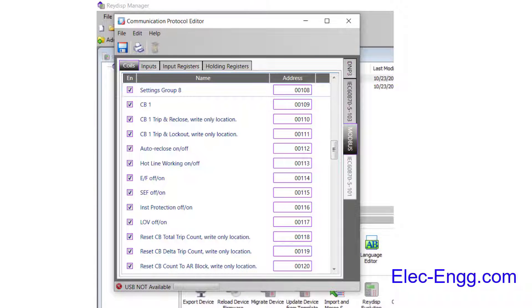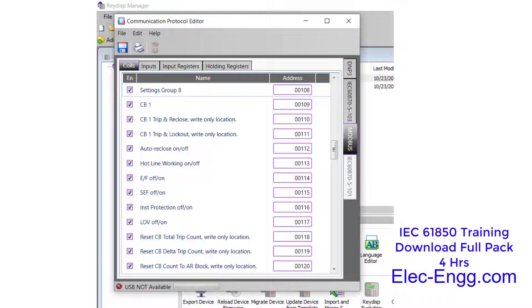Other communication protocols like Modbus, DNP3, and IEC 101 map the elements of functions to specific registers. To know the information, we have to know the address of it. The addresses are not standardized, and each device uses its own table. But IEC 61850 uses names instead of register addresses.